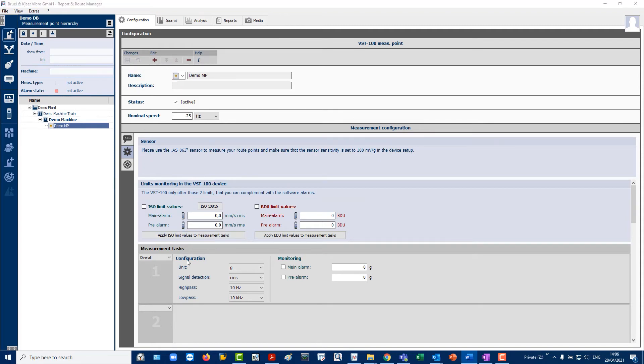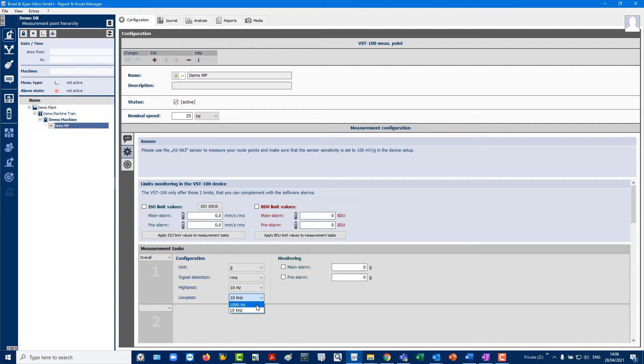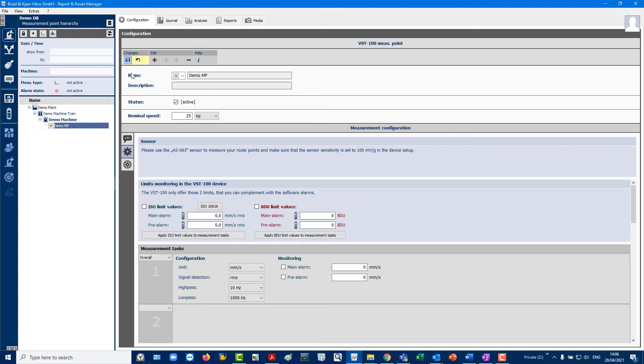Select and create additional measurement tasks in the Demo MP in the measurement task slots. Configure as follows. Task 1. An ISO 10816 overall 10 to 1000 Hz mm per second RMS.